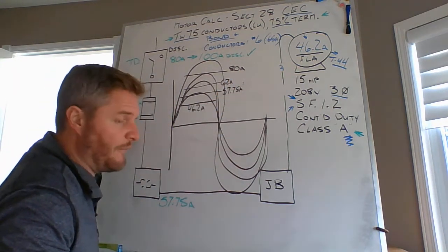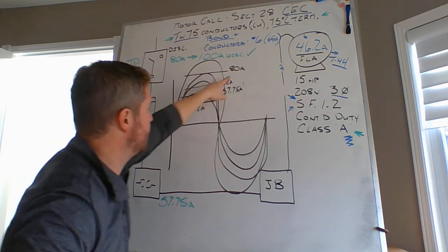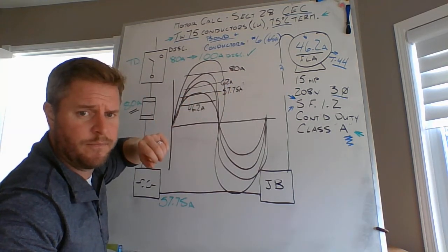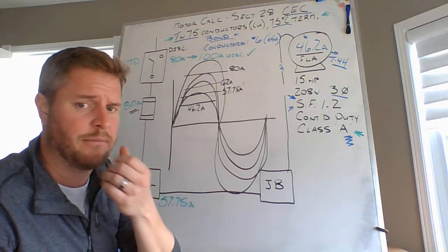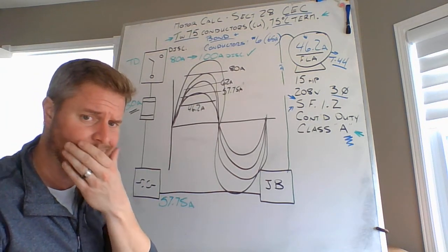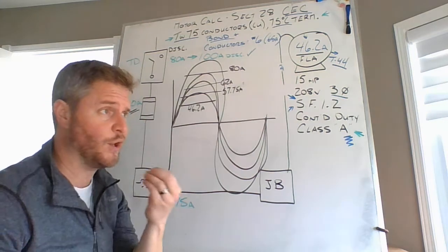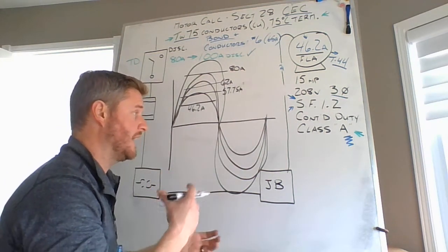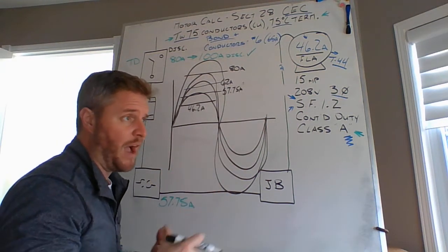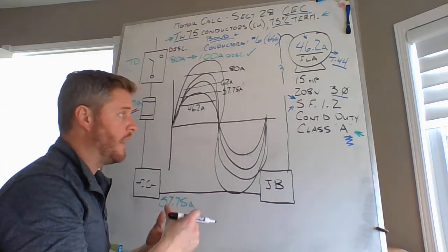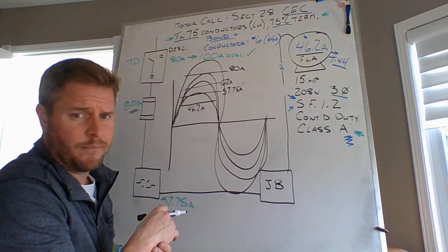The fuses are still laughing. They're saying, yeah, man, 80 amps? No problem. I'm still good. But I got a time limit. I'm a time delay fuse. So if you draw that 80 amps for, I don't know, maybe 5 to 15 seconds, somewhere in there, now I got a problem.